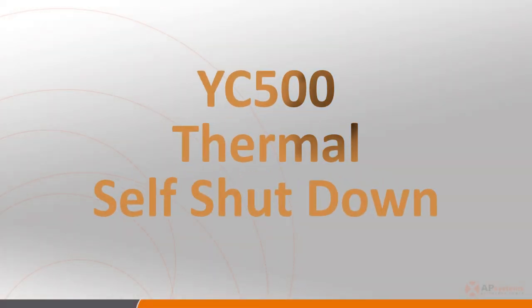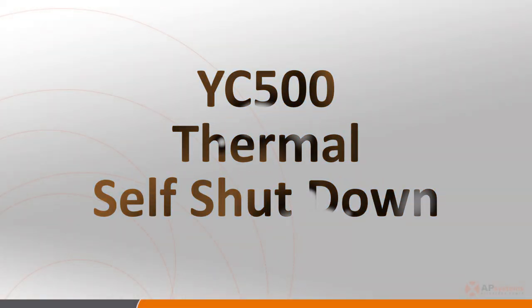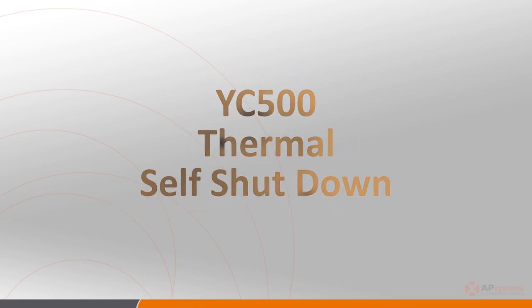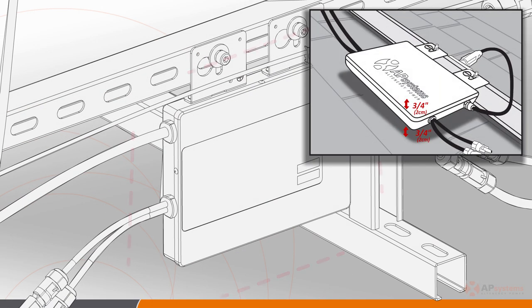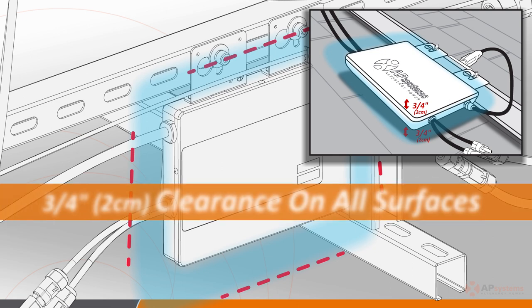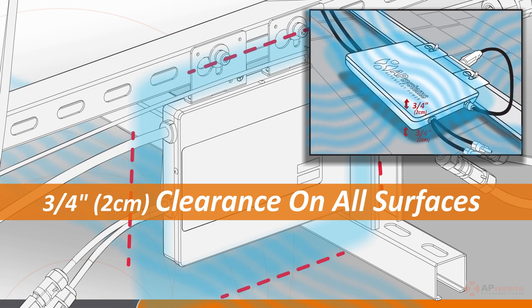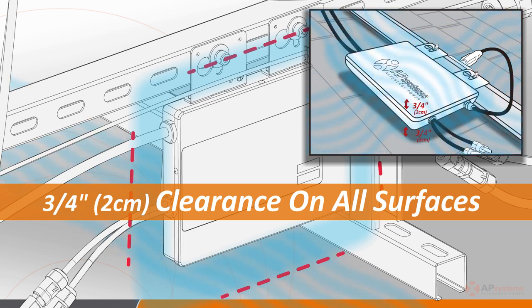As a safety measure and out of self-preservation, the YC500 will shut itself down when it reaches the upper limit of its operating temperature range. It is also extremely important to allow at least three-quarters of an inch between the roof or mounting surface and the bottom of the inverter. This spacing is important for cooling airflow to reach all surfaces of the inverter.